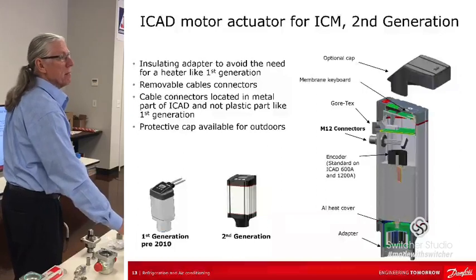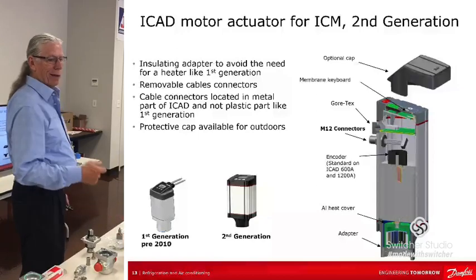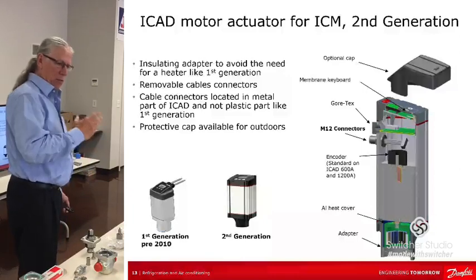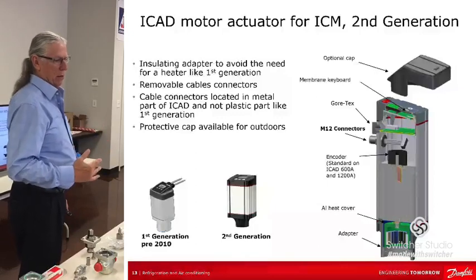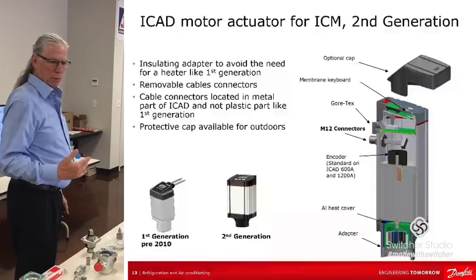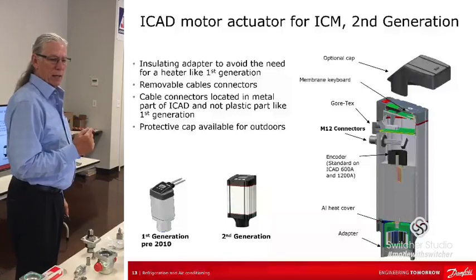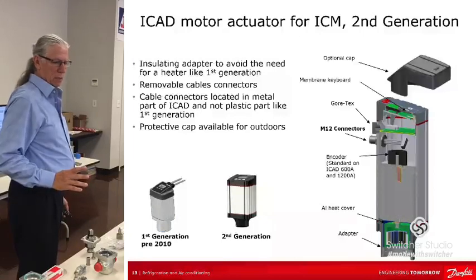The other thing is if it doesn't reset, then it could be flashing A1, CA and A3. CA meaning it's doing the calibration because you just turned the power off and back on. And A3 because it's configured, but it's not got a proper 4 to 20 input signal. Now, if it does have a proper input signal, then it's just going to flash CA and then go to the normal screen eventually. Does that make sense? Yes. Yeah. Okay.